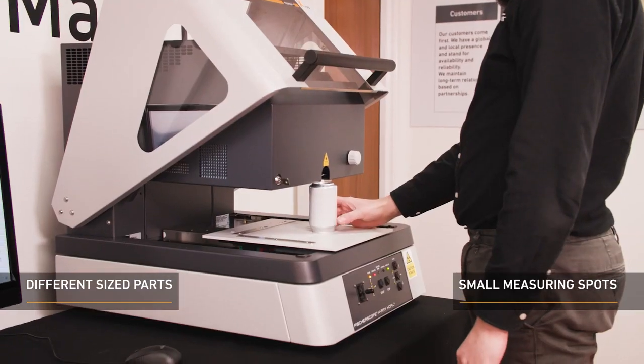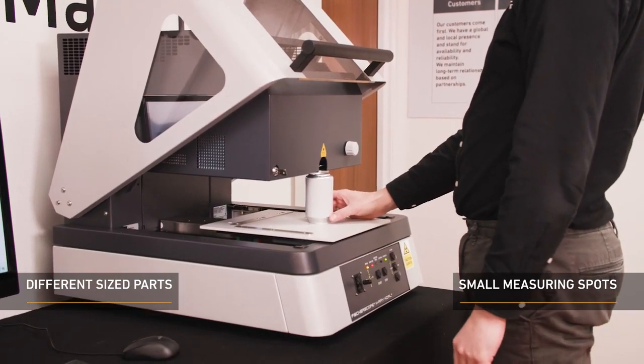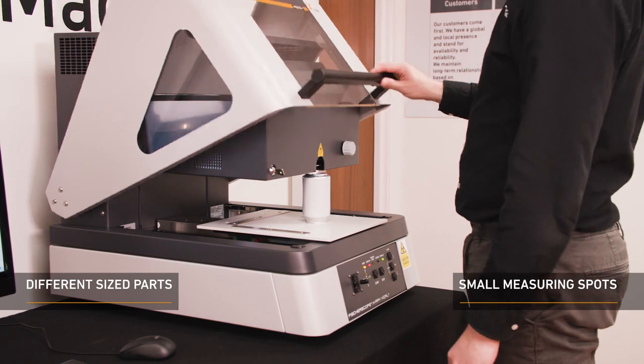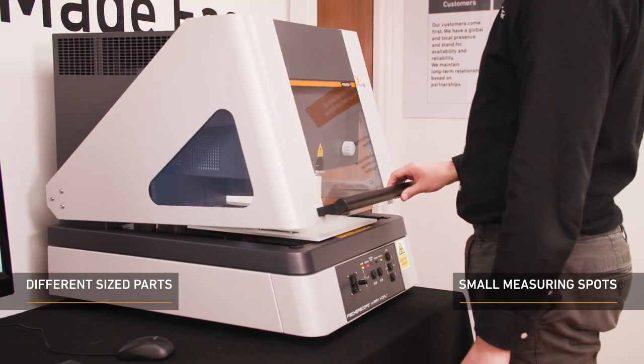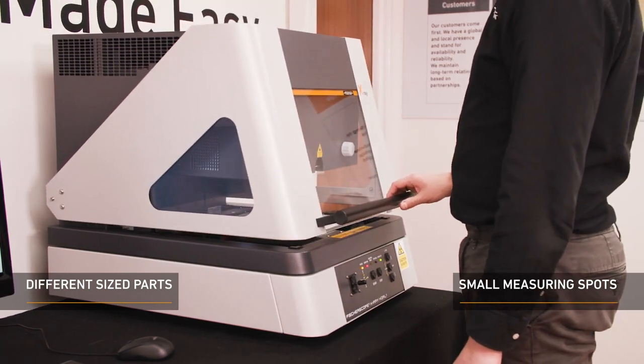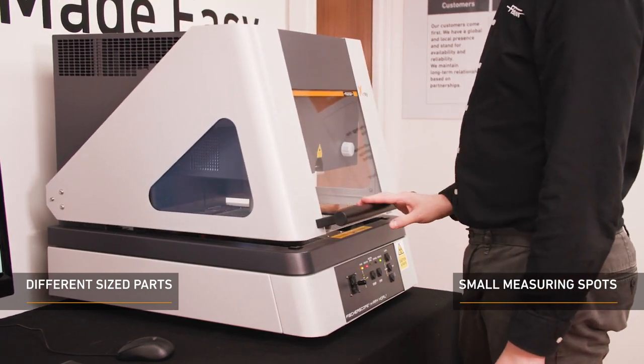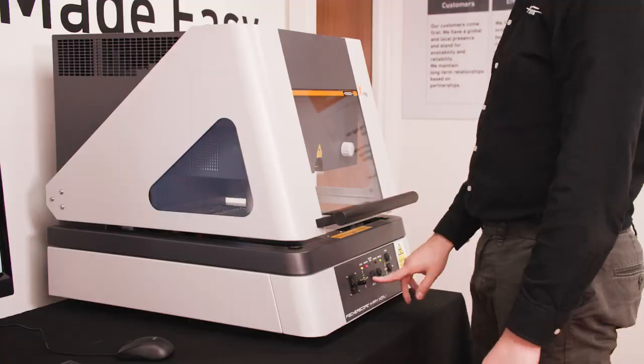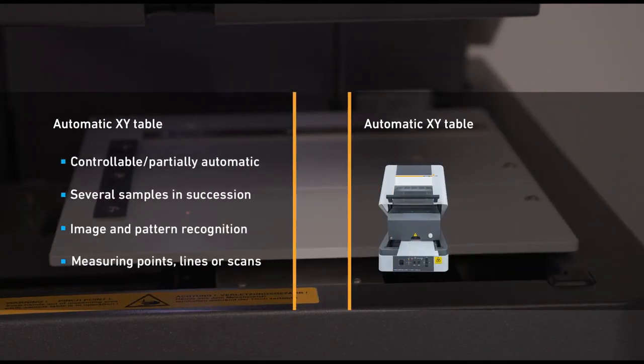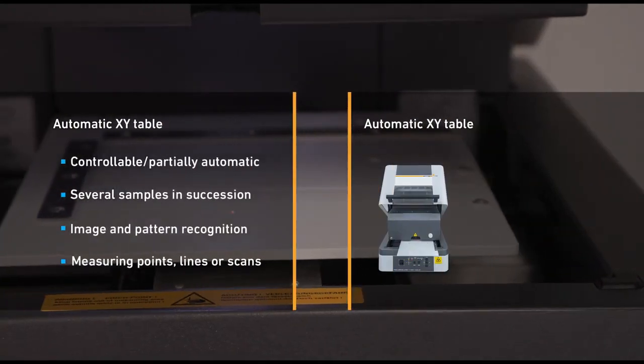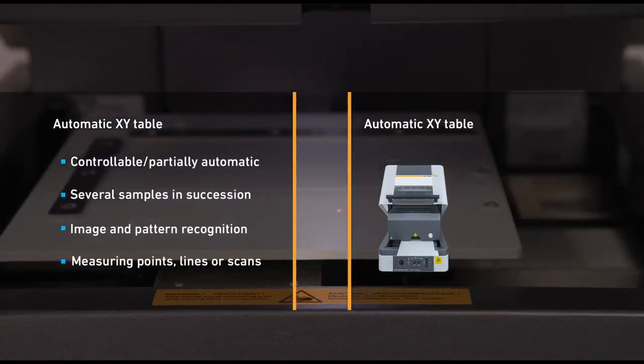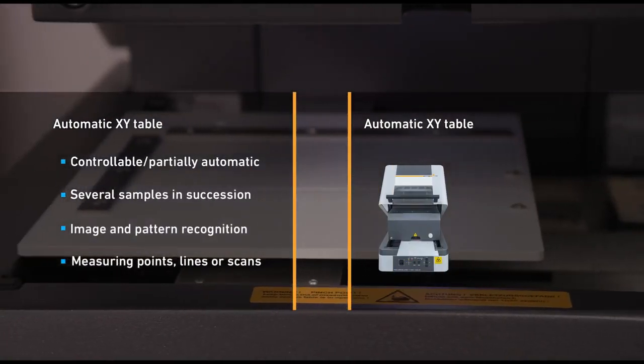It has a high-resolution video camera with zoom to enable easy sample positioning and precise measurement spot adjustment. It has a programmable XY measuring table, image and pattern recognition, and a useful C-slot gap, meaning wider-shaped parts can fit across and into the measuring chamber with ease.